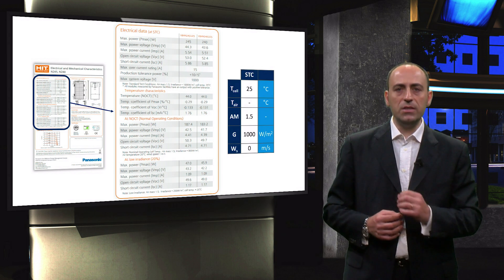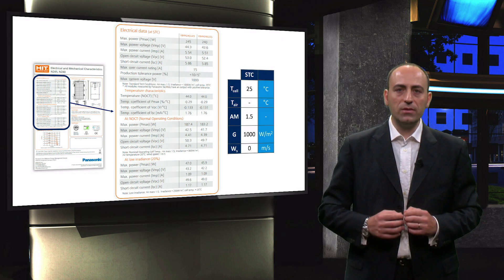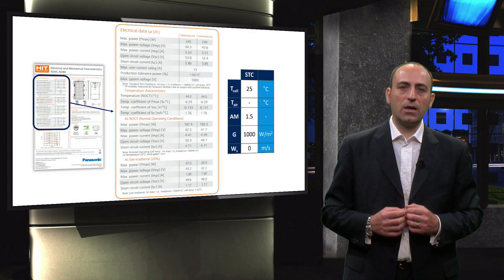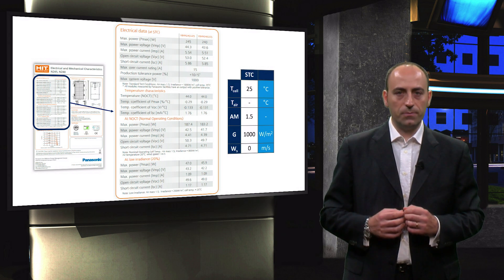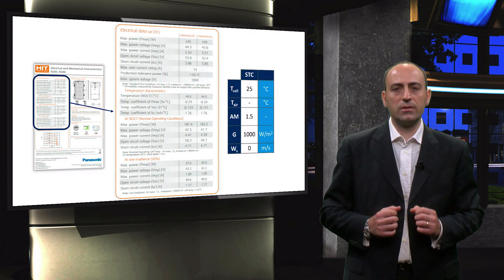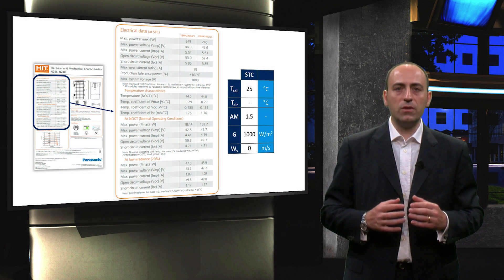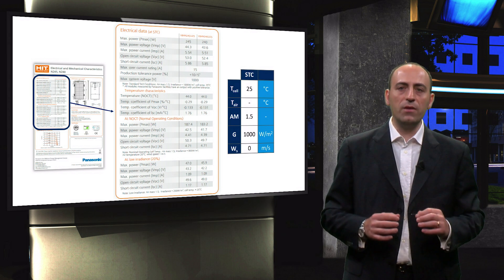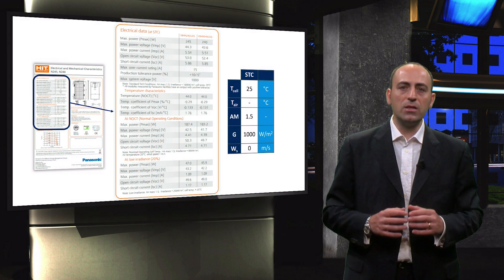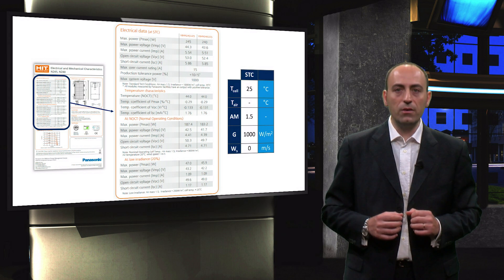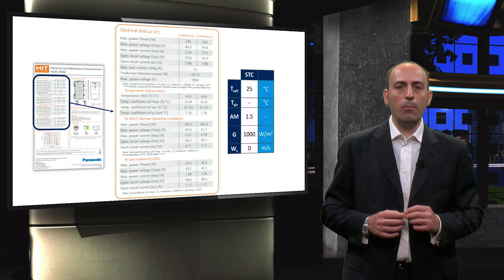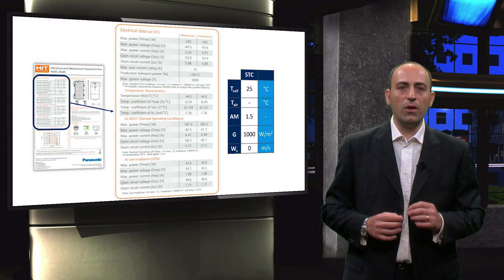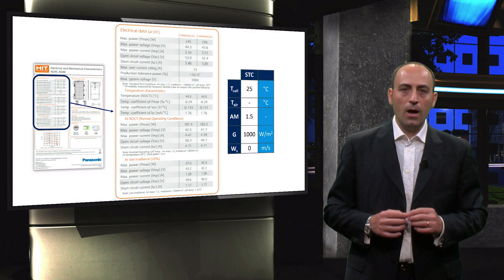Let's see what STC means. In a relevant table, electrical parameters characterized in this test are listed. During the standard test conditions, the temperature of the cell is kept constant at 25 degrees centigrade, the irradiance falling on the module is 1000W per square meter, considering the AM 1.5 solar spectrum and wind velocity 0.